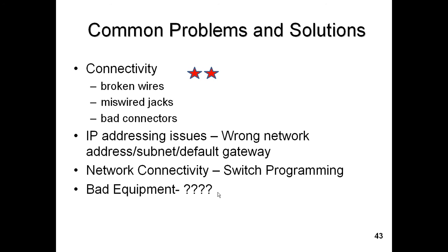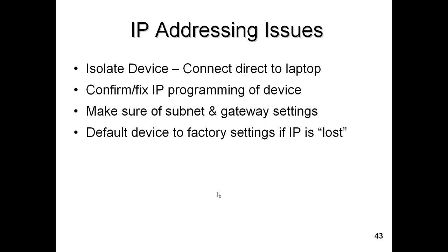And you may have to work with the IT people, to make sure that the female sockets on the switch that you're plugging into are active, that they're turned on. Maybe that's something the IT person has to do for you. Now you notice down here at the bottom I've got bad equipment? The manufacturers in our business uniformly build good equipment. Very rarely, unless we misapplied power and made the smoke come out of the box, does the equipment fail. You should know how to default your device back to its factory settings. If the link light's lit, chances are the equipment is not defective.